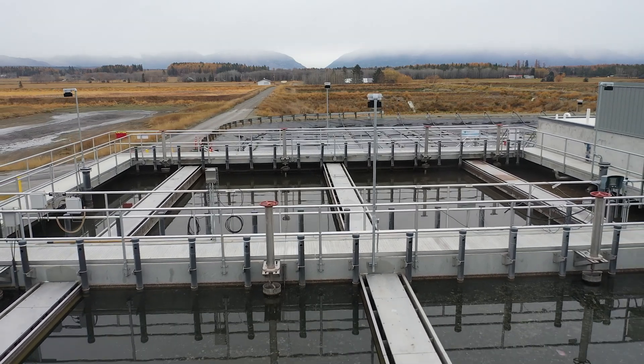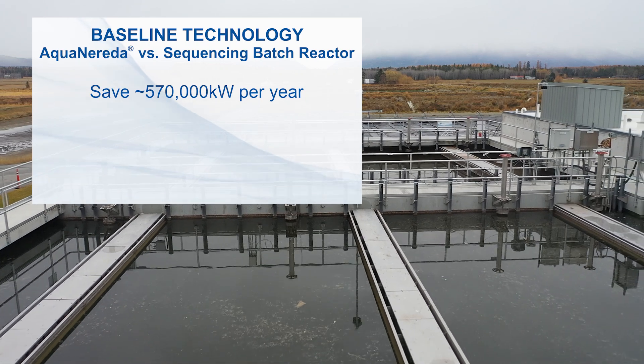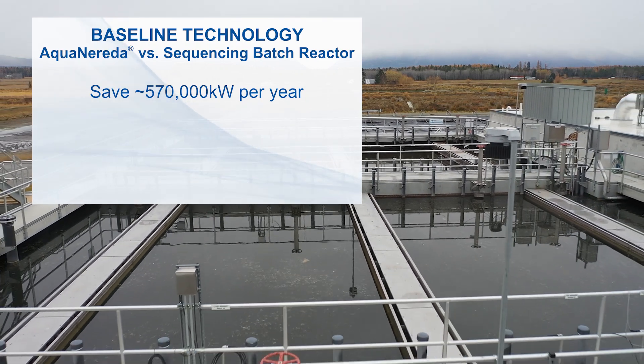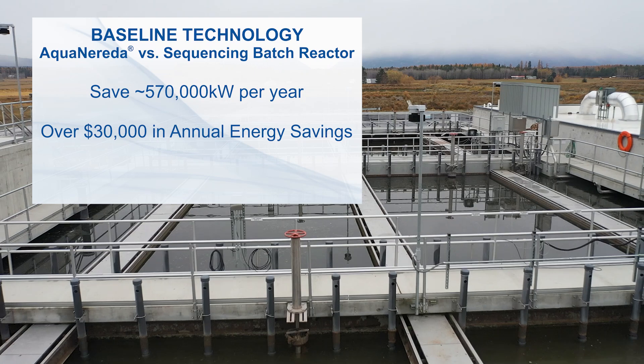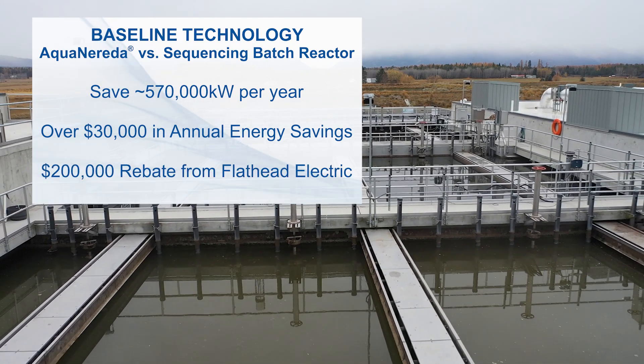The city worked with their local electric provider, Flathead Electric, on a rebate through their Energy Smart industrial program. We looked at a baseline technology — a traditional SBR — and compared that to the AquaNereda system that was chosen. By choosing the AquaNereda system, we save about 570,000 kilowatt-hours per year. That translates to over $30,000 in annual energy savings and netted about a $200,000 rebate from Flathead Electric.